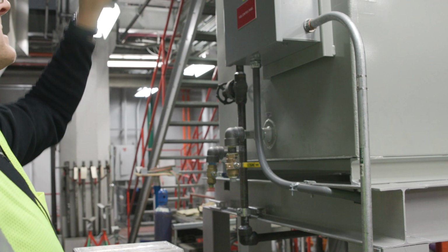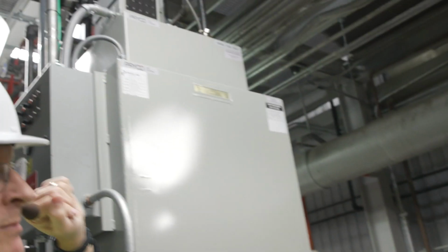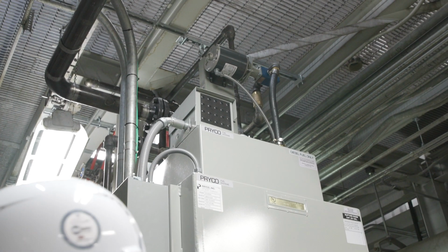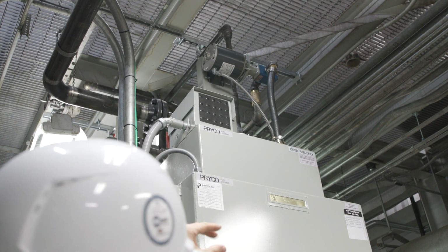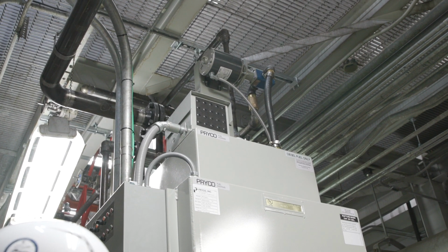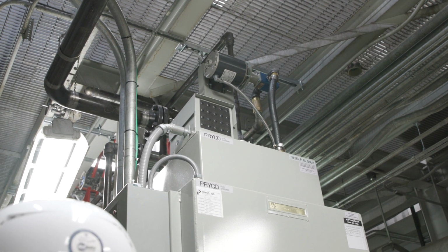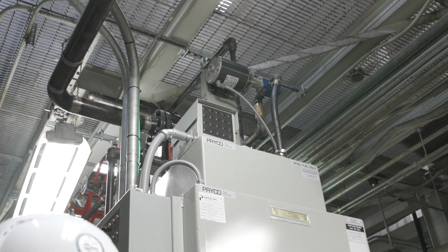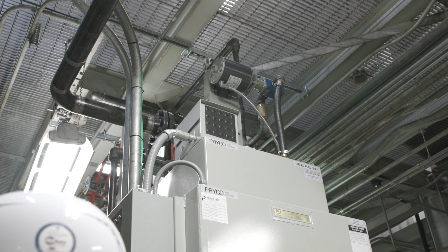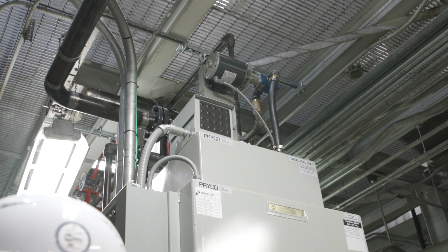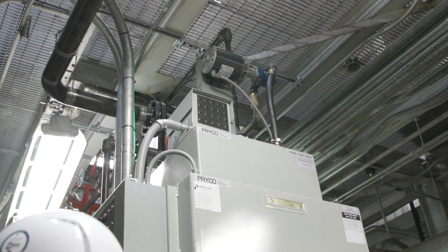And then you've also got on top, it's kind of hard to see, but you do see the return pump. That return pump will come on when we get a critical high level. And then it's also hard to see, but there are 2 sets of supply valves that will open whenever we call for fuel. And we'll send a signal to pressurize the line and open those valves so that we can fill the main tank from your bulk tank.